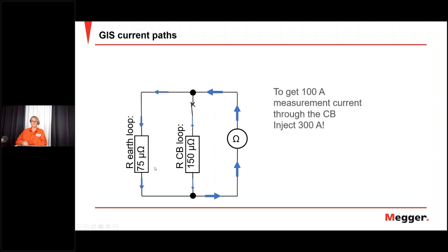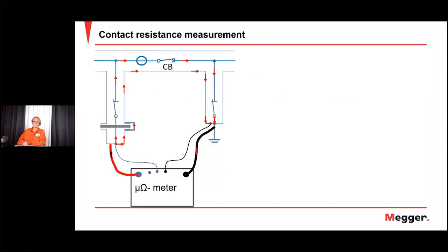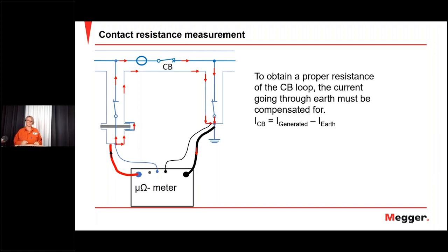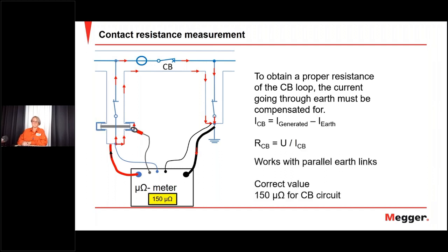So you inject, and you want to inject 100 amps to follow the American standard there, you need to inject 300 amps, or if you want to follow IEC, you will need to inject 150 amps. 300 amps will go from your instrument, but only 100 will go through the circuit breaker loop, and 200 through the earthing loop. So to get the correct result here, you need to remove the current from ground. So you need to use current clamps. And in this case, there are two paths. And you can measure the correct value.